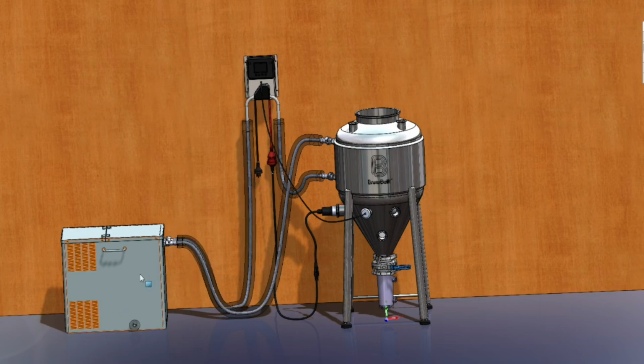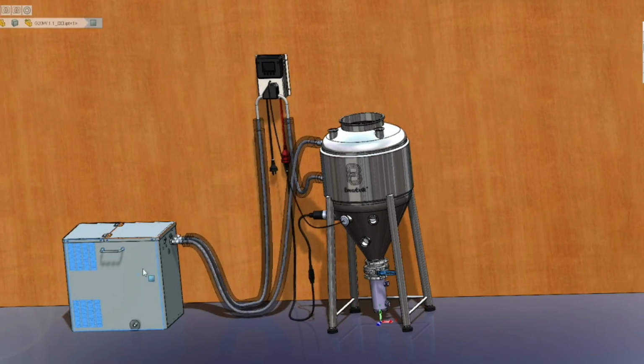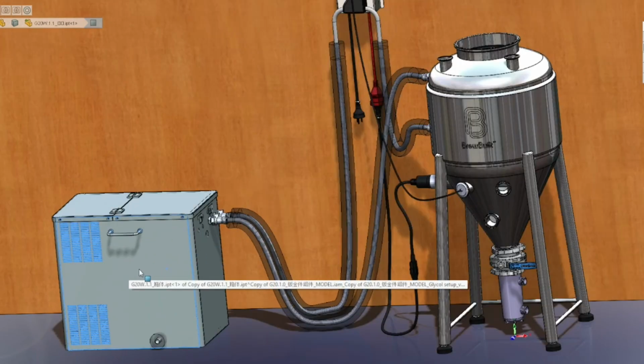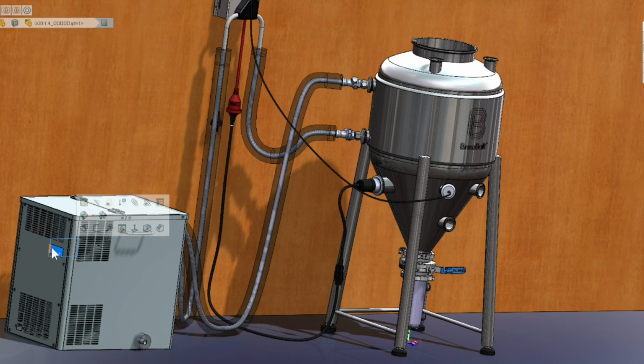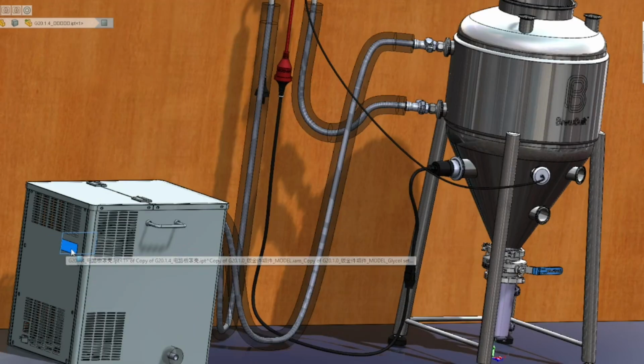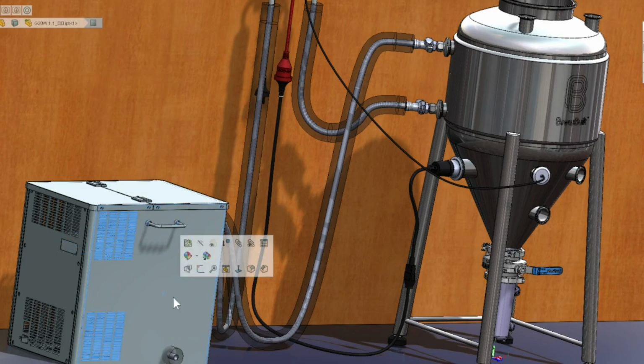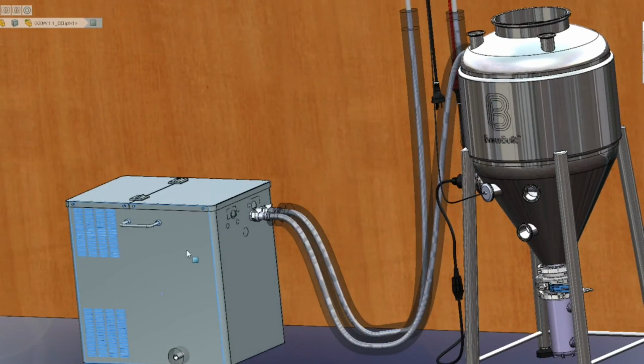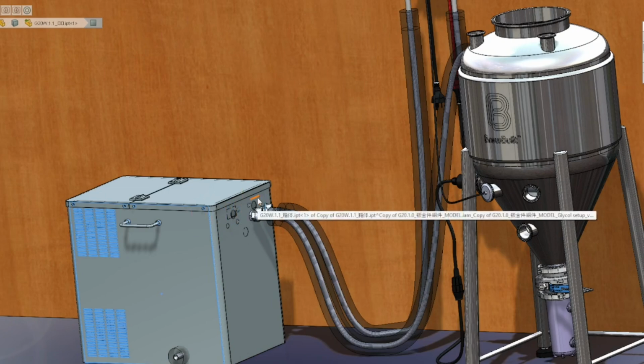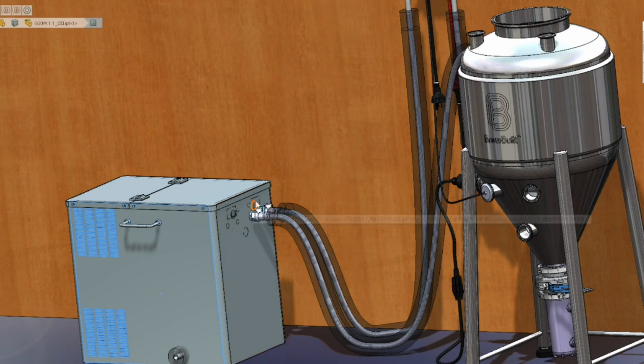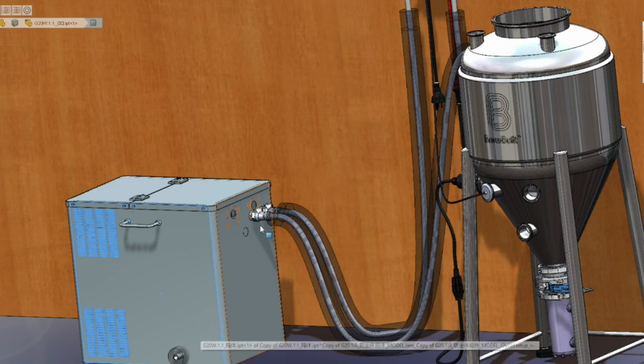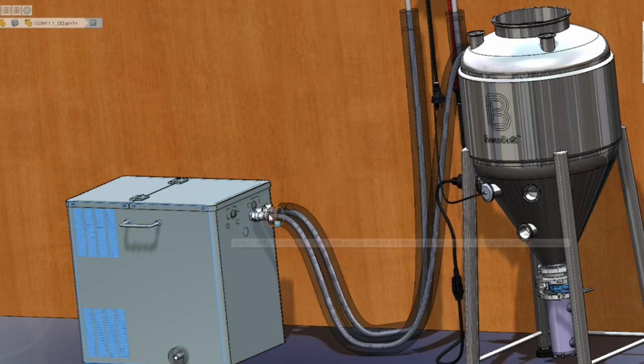Previously, our Glycol chillers looked something like this model of our G20. We also had a G40 Glycol chiller, which was also pretty popular. But this type of solution had a few limitations. On the back of the Glycol chiller we had a temperature controller that set the temperature of the glycol sitting in the bath. On the front of the unit we'd have a couple of different output temperature controllers. On the G20, you'd have up to 2 temp controllers on the front, and depending on the set temp you put into these digital controllers, that would cycle a pump inside the glycol bath to pump glycol through either output number 1 or output number 2.